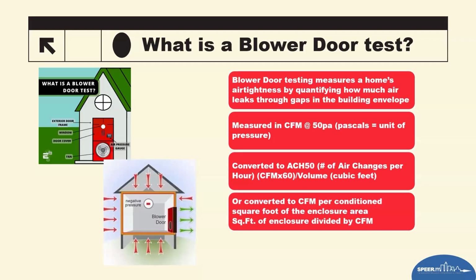I won't go through what all those are because the targets vary by climate zone and code cycle. They were roughly the same for a long time. Now it's being adjusted in the 24, and it'll continue to tighten the building envelope as we go into new code cycles. The second method is getting CFM per square foot of conditioned enclosure surface area. That includes the walls, the floors, the ceilings. The total surface area is divided into the CFM to get a 0 point something value. Right now we're looking at like 0.30. That is how much CFM is happening per every square foot of conditioned enclosure surface.